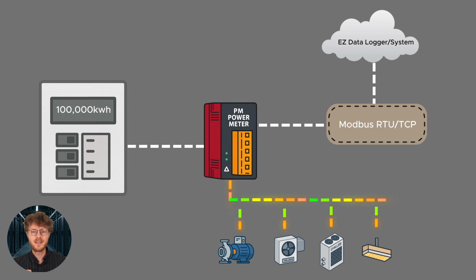They work by measuring current and voltage on a circuit. Using current transformers or direct connections, the meter calculates power usage, energy consumption over time, and can even track things like power factor, harmonics, or demand loads. The readings are then stored inside the meter and communicated back to your system either over Modbus TCP or Modbus RTU. In order to be operated, a PM power meter simply needs a power source, a connection to your circuit, and a communication path. Whoa, that was a lot of information, but don't worry, I know it can get confusing, so I'm gonna make it super simple.